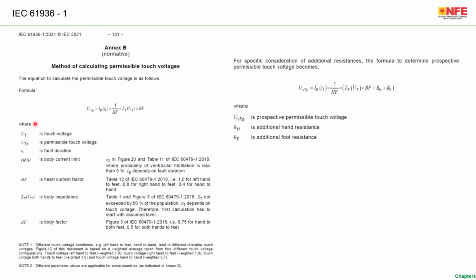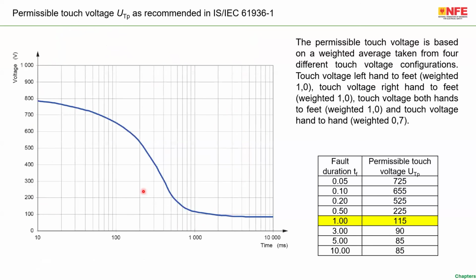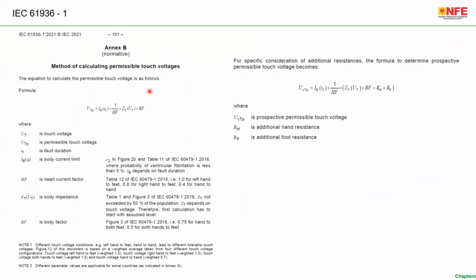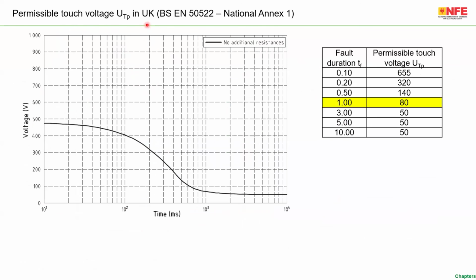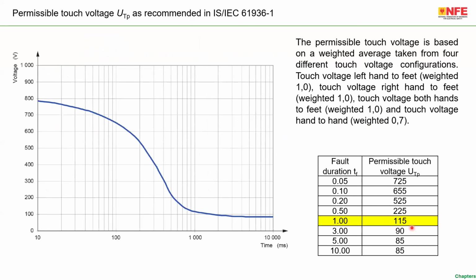Now the standard also explains how to calculate the touch voltage and prospective touch voltage. If a country or any installation needs a touch voltage other than this particular graph, you can use these calculations and arrive at a figure which is different. For example, in the UK, the BS EN 50522 in the national annex uses a different touch voltage chart. As you can see here in the IEC chart, at 10 millisecond the touch voltage is about 800 volt, whereas here they have reduced it to something below 500 volt. For example, at 1 second in the UK, the touch voltage has to be reduced to less than 80 volt, whereas in the IEC standard, what is recommended is less than 115 volt.